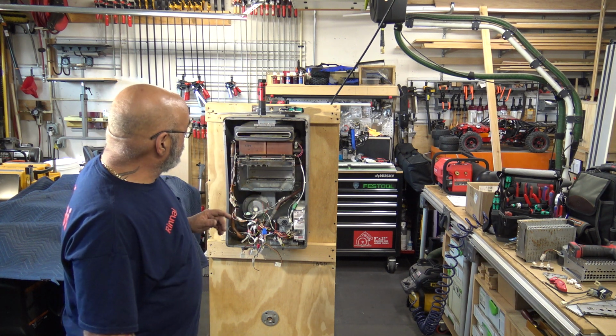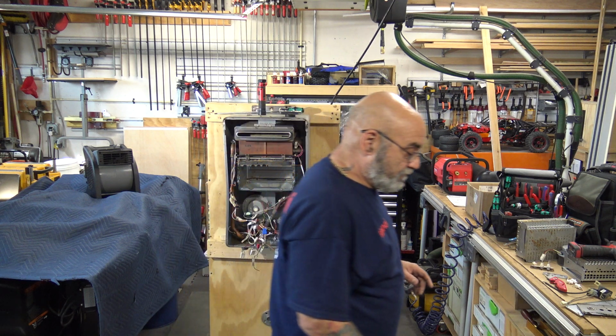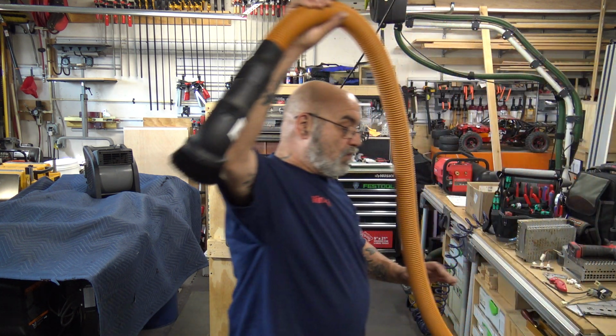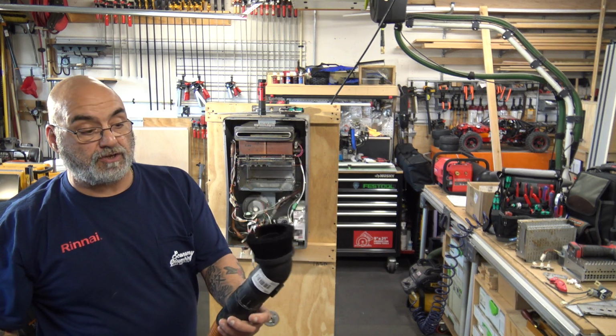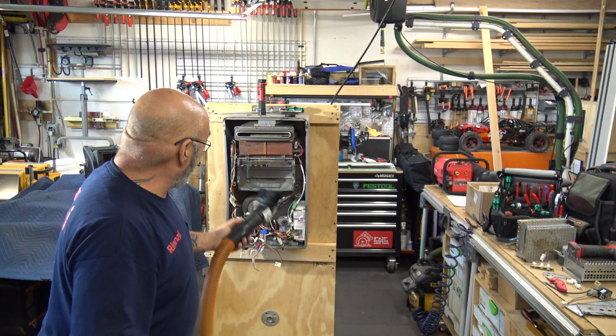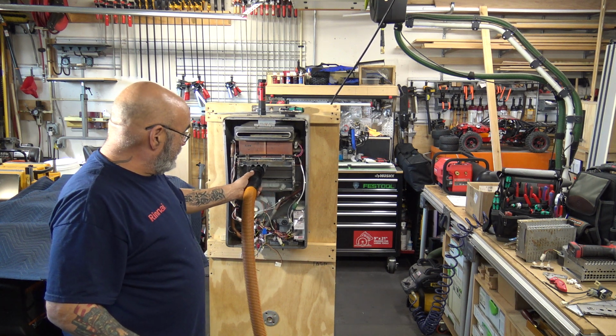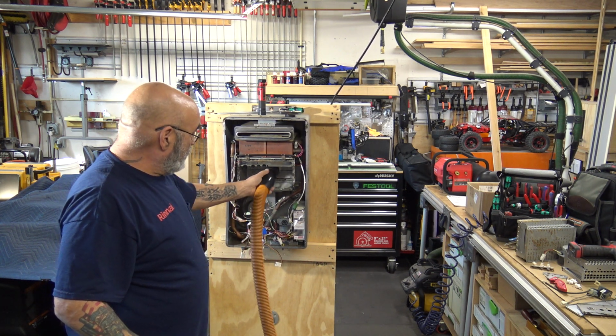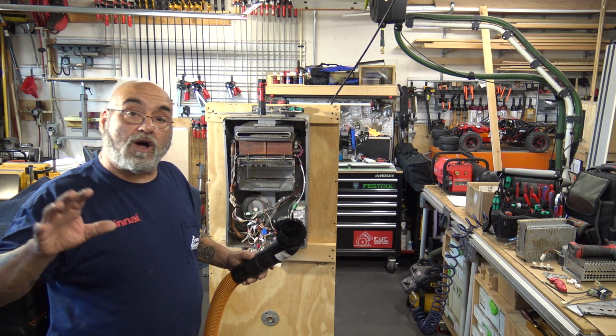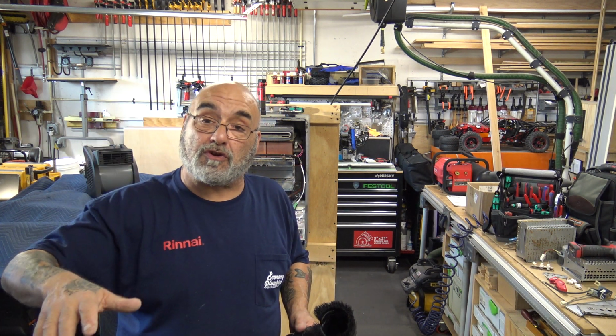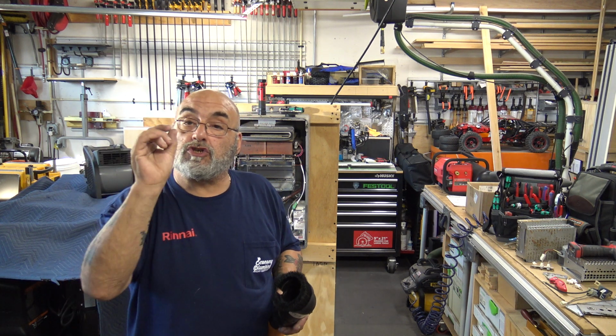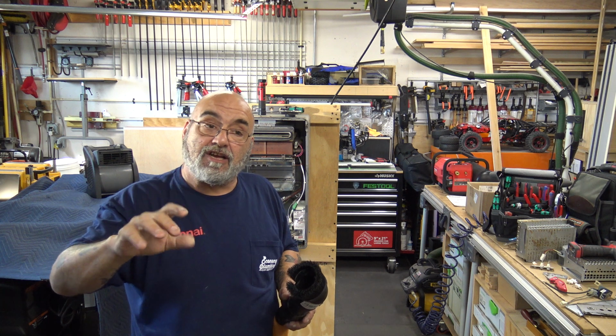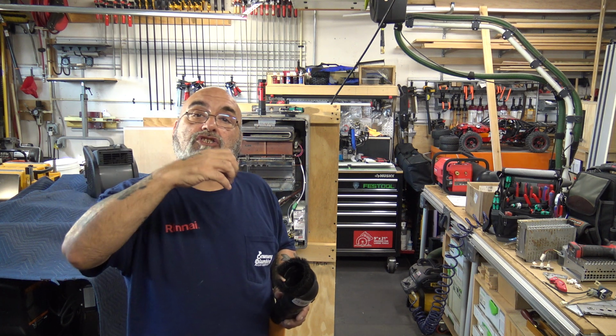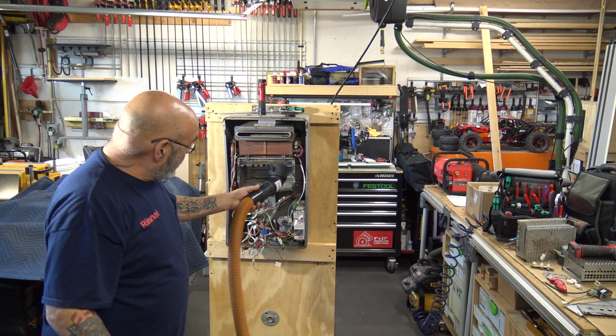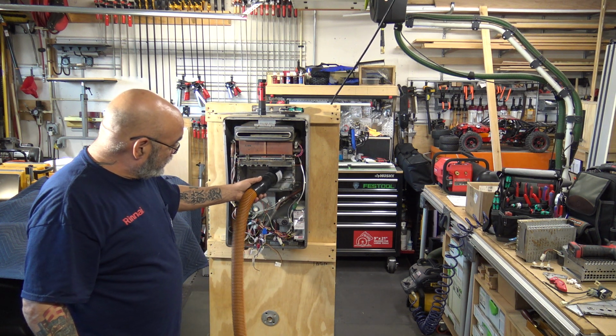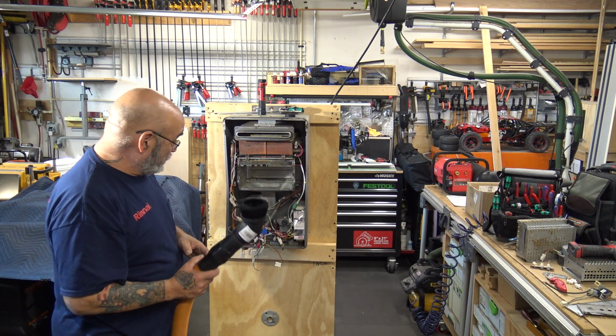So first, what you want to do is vacuum the unit, but you don't want to vacuum it with a hard bristle brush. You want to vacuum it with a soft bristle. So you want to get up in there with the vacuum and start vacuuming, moving the bristles around. You don't want to use a wire brush, a screwdriver, or anything else, because you don't want to bend the heat exchanger fins. If you bend them, you reduce the surface of the heat exchanger. So you want to get in there with this brush and brush it, brush it, brush it, get in here and brush it.